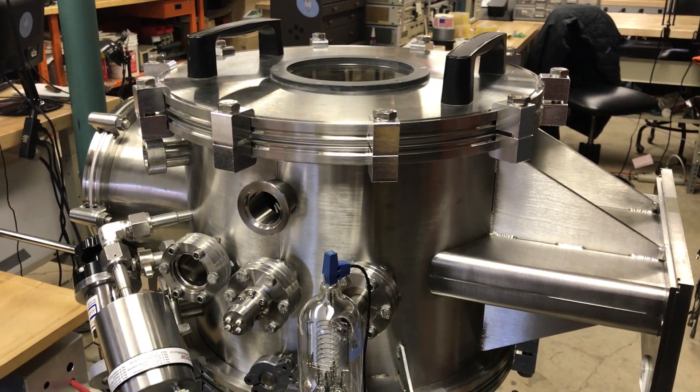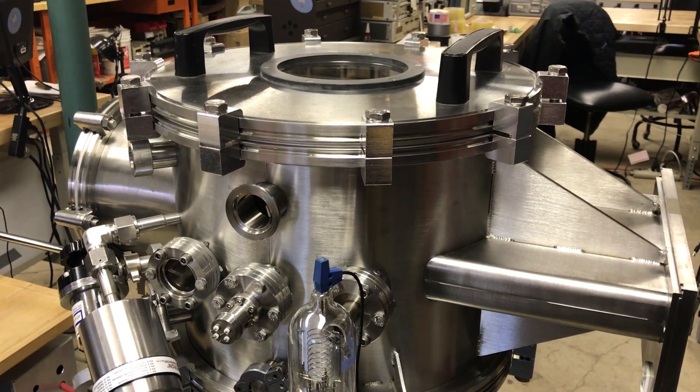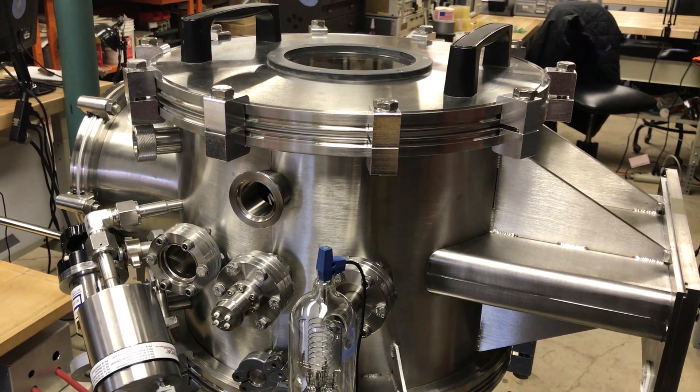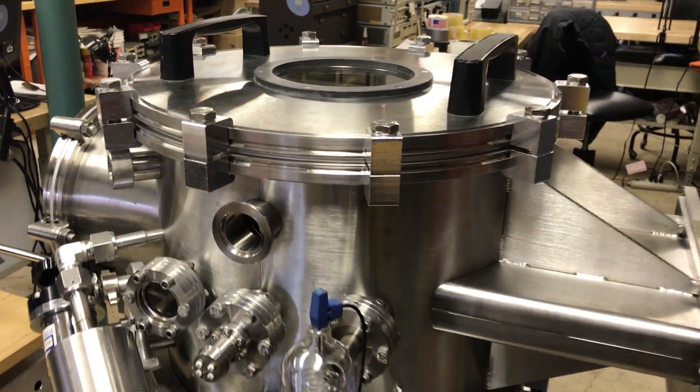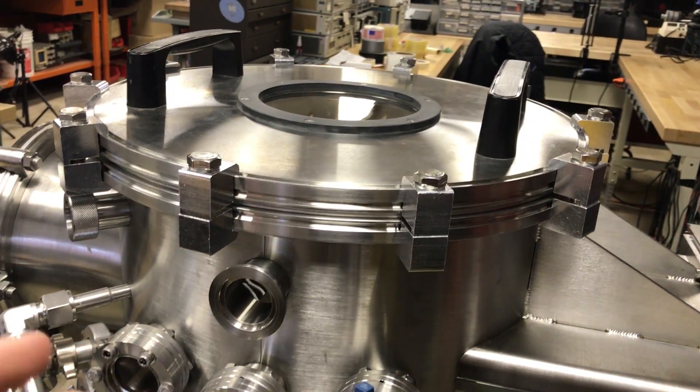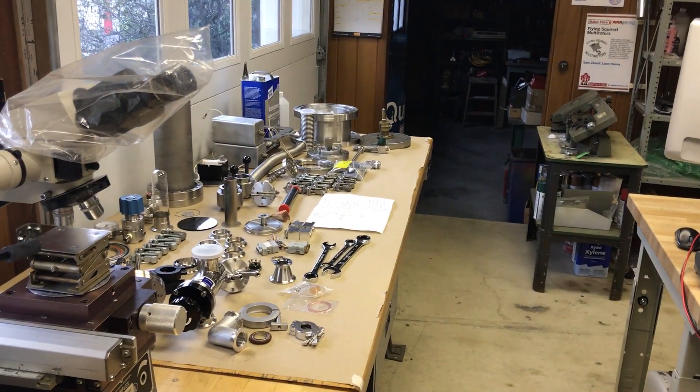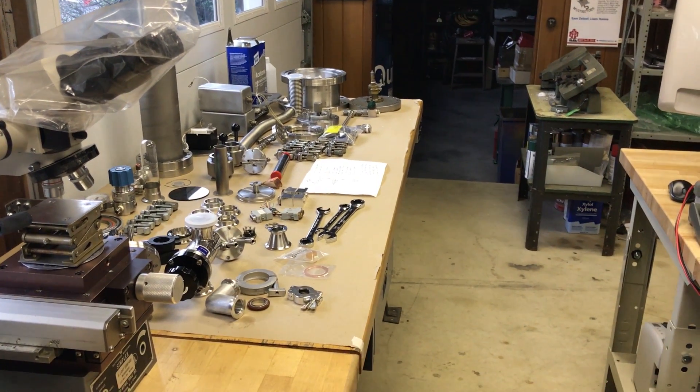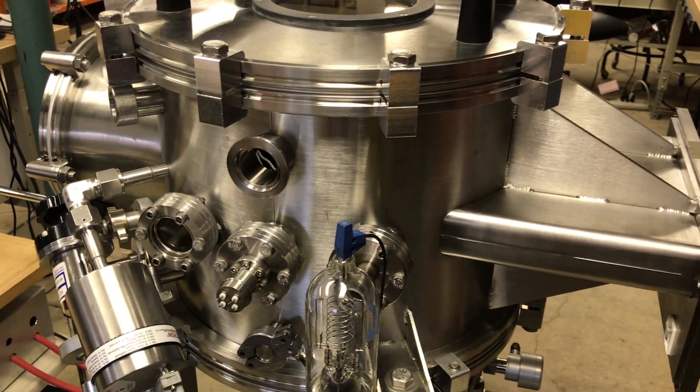First thing, when you're working on this kind of stuff, you should always wear gloves. Even nitrile gloves are good, but you want to prevent putting your fingerprints on any surface that's going to be exposed to vacuum, especially on the inside of the chamber. So even when you're just handling flanges and such, you should always be wearing nitrile gloves, and that just prevents a lot of unnecessary cleaning afterwards.